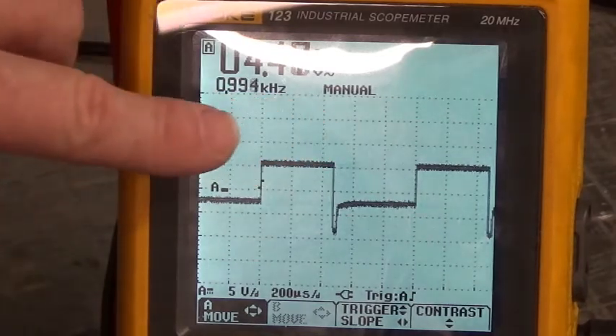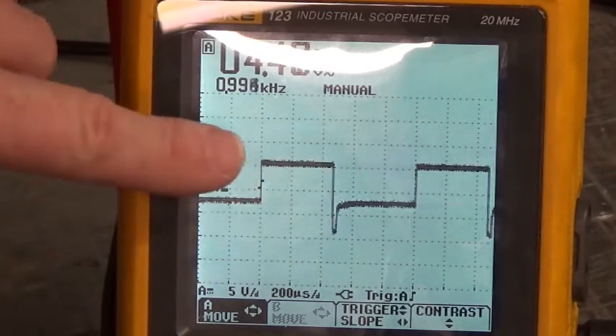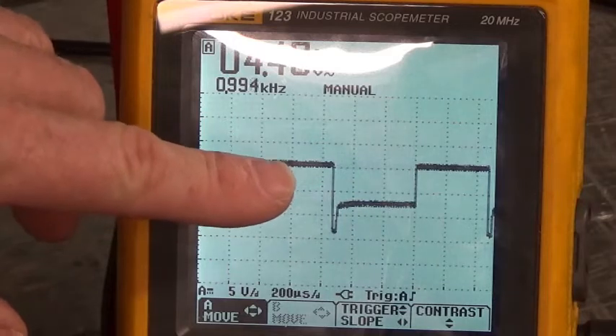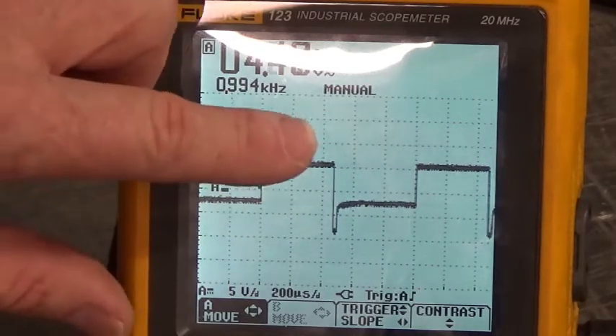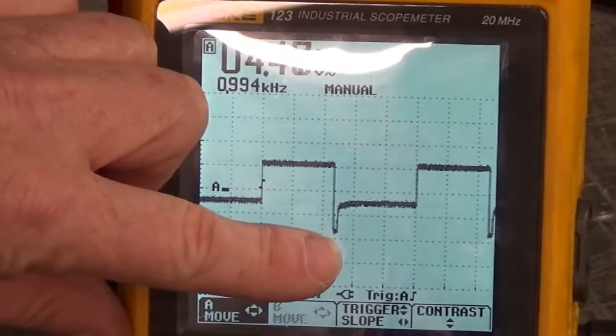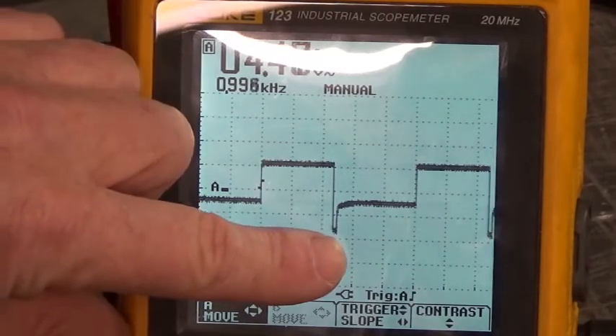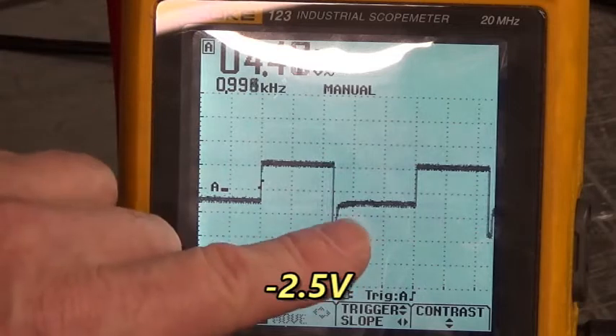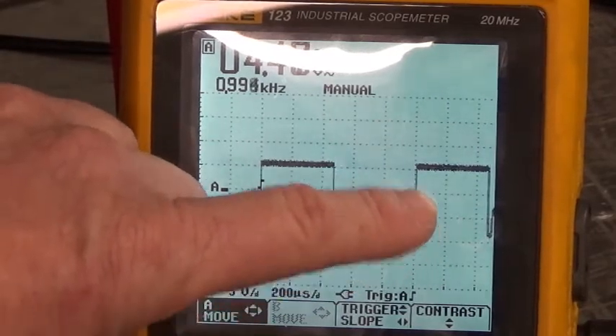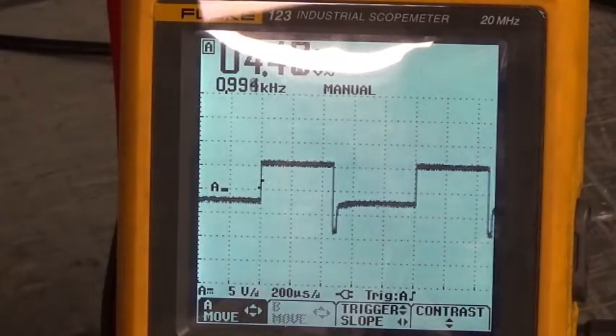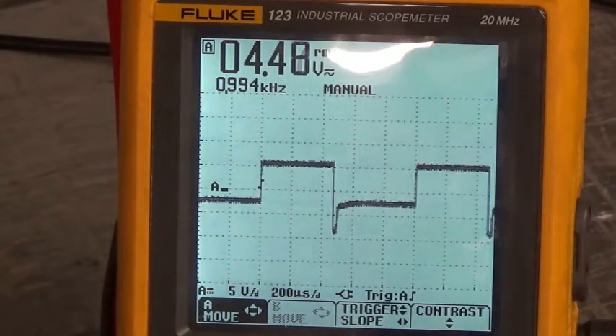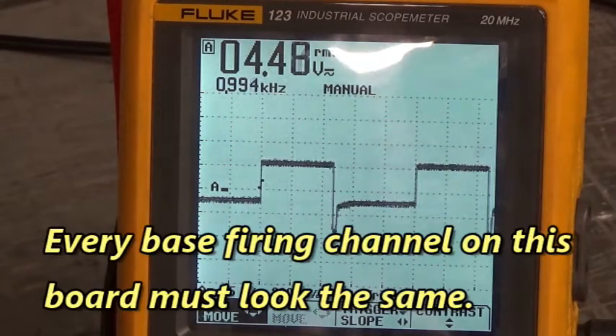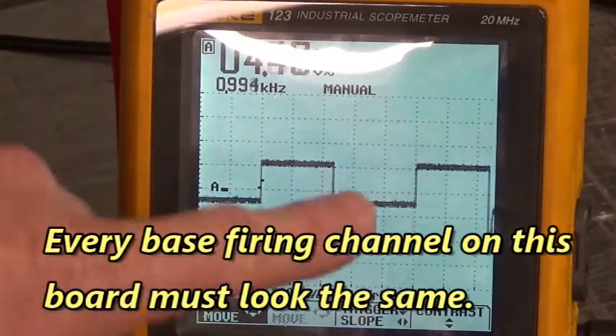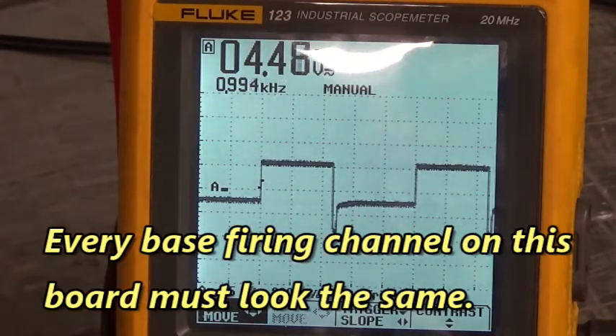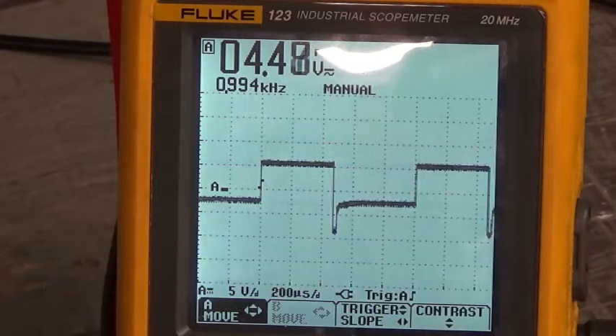The peak of the base firing waveform here is at about 6 volts peak. Then it dips down to about -7, -8, comes back up to about 2.5, and then shoots back up to a peak of 6 volts right there. Every channel that you look at should look like this right here. If it does not look like this, there's a problem in that firing channel, and you have to go in there and fix it.